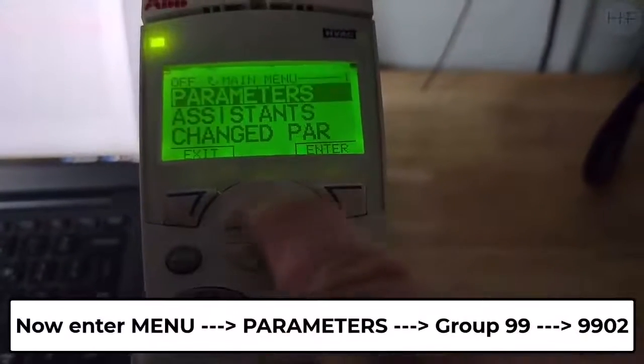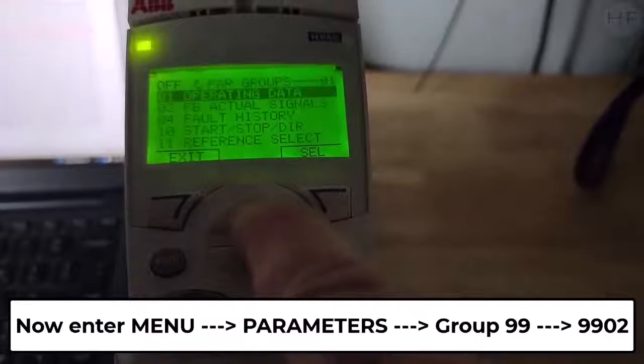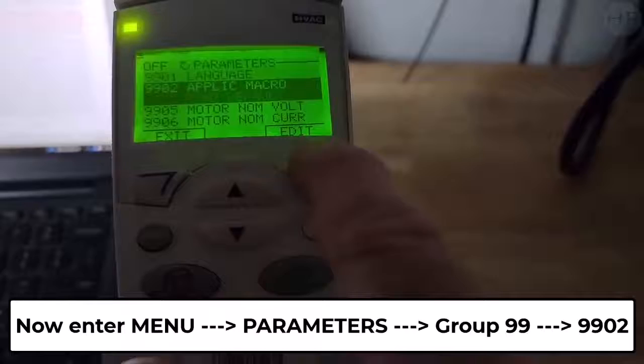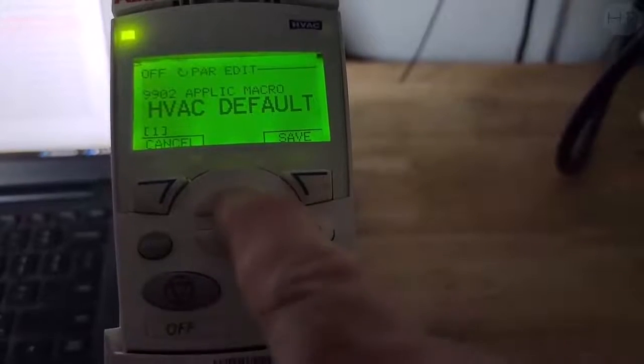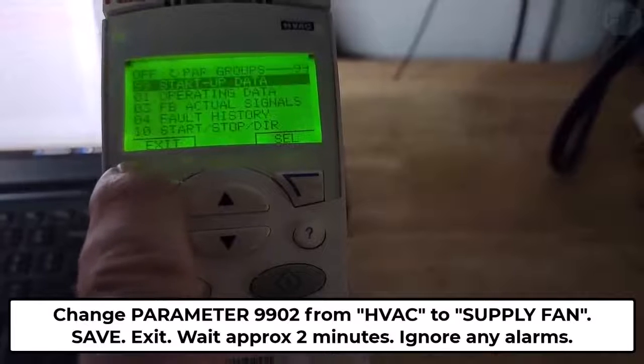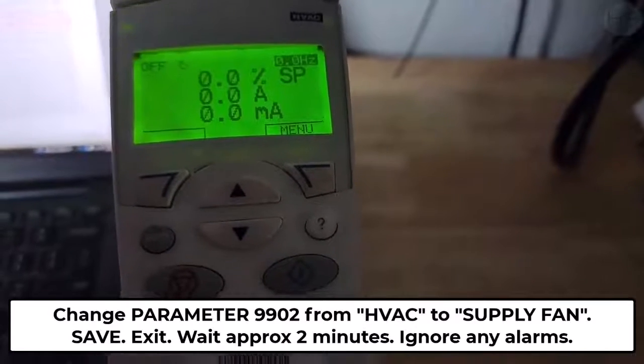Now enter menu, parameters, group 99 and find parameter 9902. Change parameter 9902 from HVAC to Supply Fan. Save, exit and then wait approximately 2 minutes.